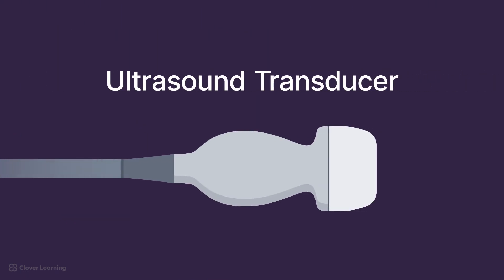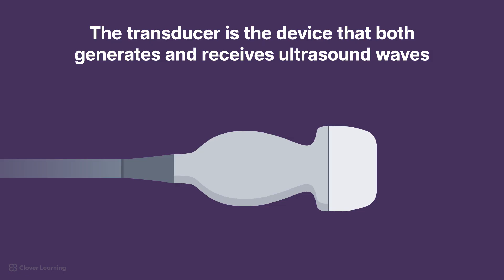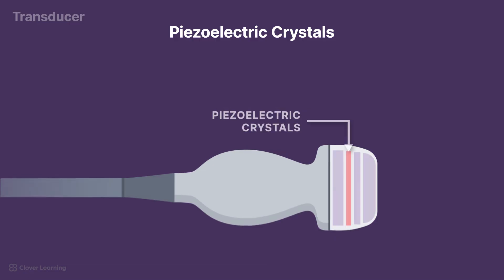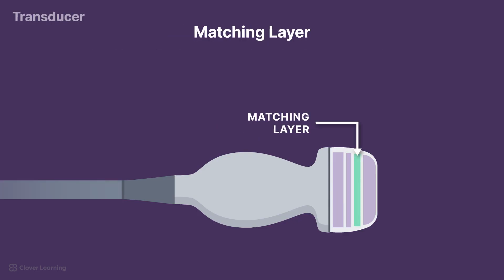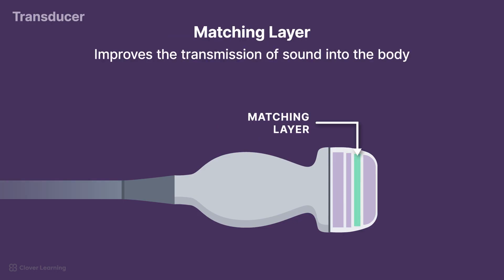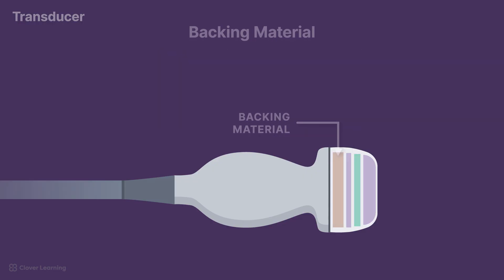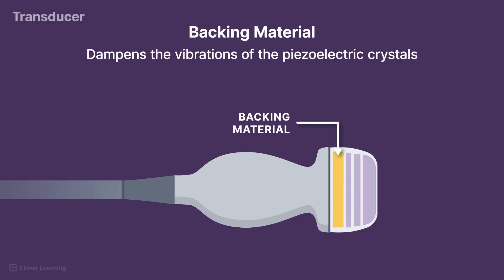Let's take a closer look at an ultrasound transducer. The transducer is the device that both generates and receives ultrasound waves. Its basic parts include piezoelectric crystals, which convert electrical energy into mechanical sound waves and then turn the echoing sound waves back to electrical energy again. A matching layer improves the transmission of sound into the body. Backing material located behind the crystals dampens the vibrations of the crystals.